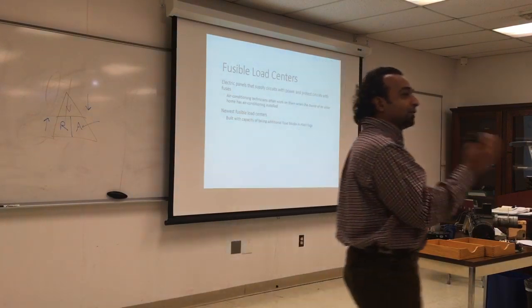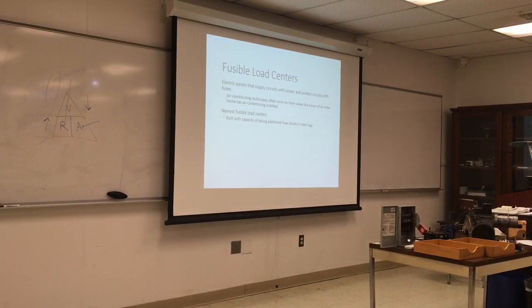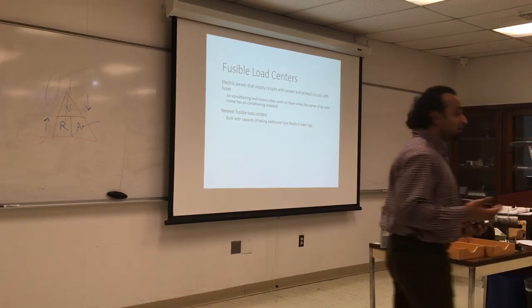So, what I was asking, usually when you go to a power plant or a refinery, they put all the disconnect switches in one room for accessibility. You want somebody in the control room to be able to shut off each piece of equipment if they need to. You cannot be running around the plant to turn things off. You want things centralized so you know what power to shut off.